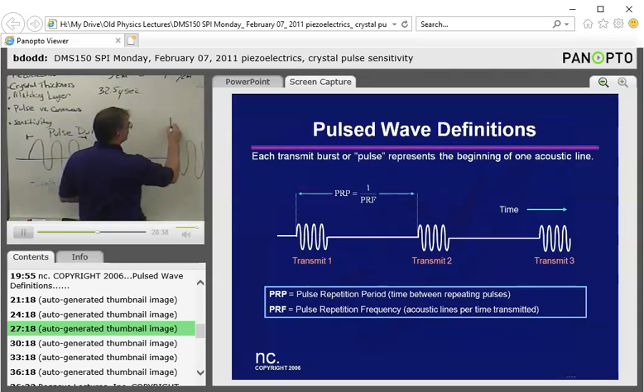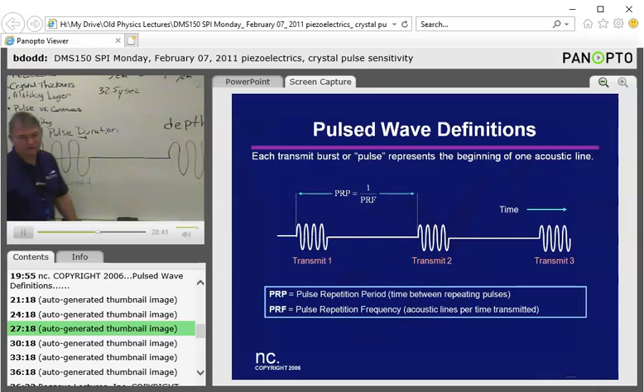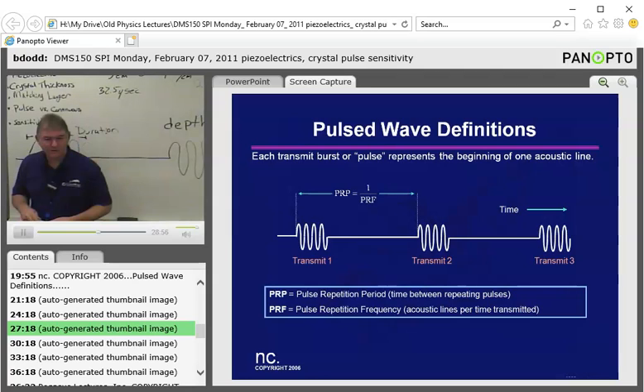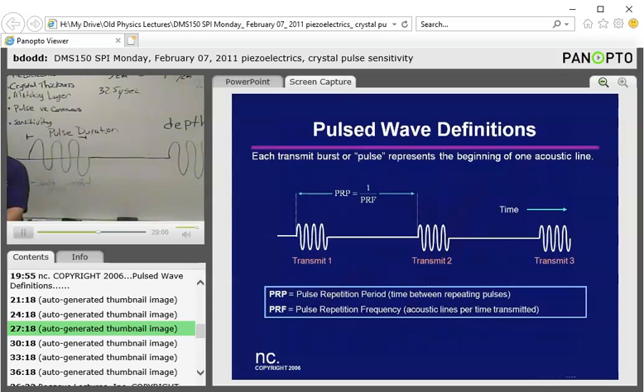Another way to put it is it controls my depth. The pulse repetition frequency controls the depth. How many times per second I can send out a signal controls how deep I can scan. If I'm only scanning 1 centimeter deep, so if I'm sending out only a pulse to the first aisle, to the first person, then I can send out a lot more pulses than if I have to send it all the way back to Diana in the back there. Okay? So really short pulse repetition period, very high pulse repetition frequency. If I'm sending it all the way to the back, I have to have a very long pulse repetition period, and it's going to be a very low pulse repetition frequency.